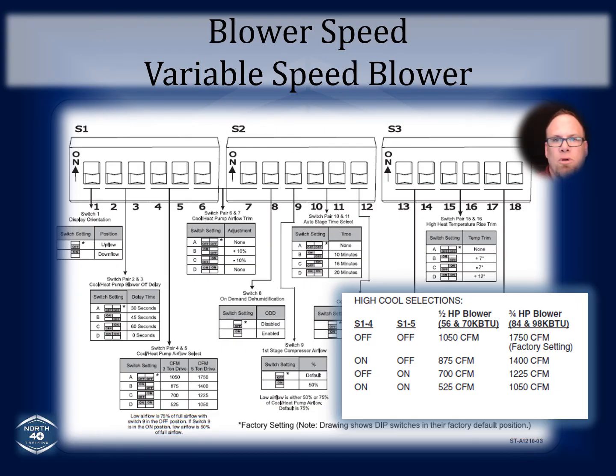Okay, here's an example of the manufacturer's diagrams on how to adjust the blower speed. If you look at the switch banks at the top, we got switch banks 1, 2, and 3. And if you look at the cooling selections here on the little breakaway chart, just off of the left-hand side of where I am, you'll see the cooling selections. And they tell you whichever size blower you've got, that's going to be the corresponding CFMs for your configuration of dip switches. Okay, so if you've got the 56,000 or the 70,000 BTU furnace, then you're going to have a half horse blower, and your configurations of switch bank 1, dip switch number 4, and dip switch number 5, both in the off position, will be 1,050 CFM.